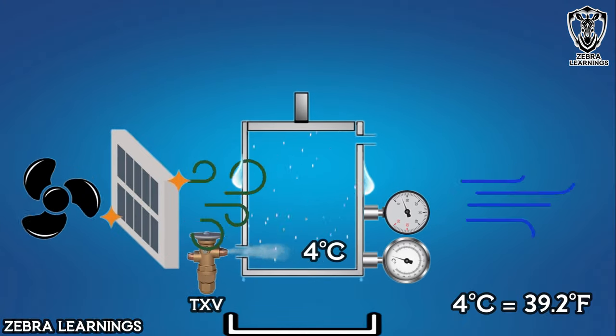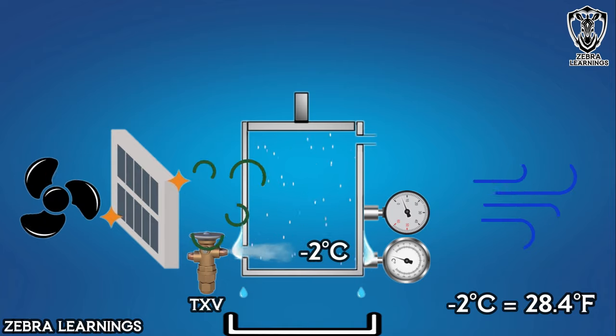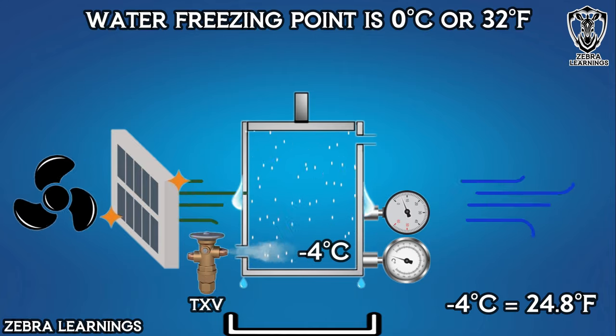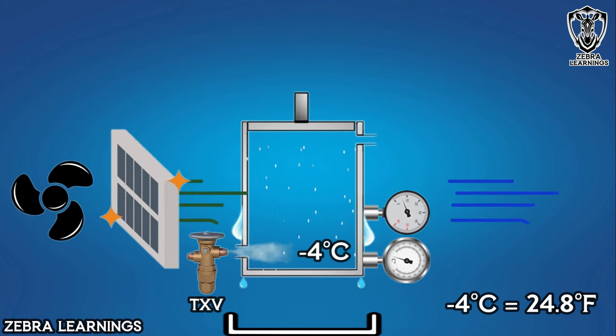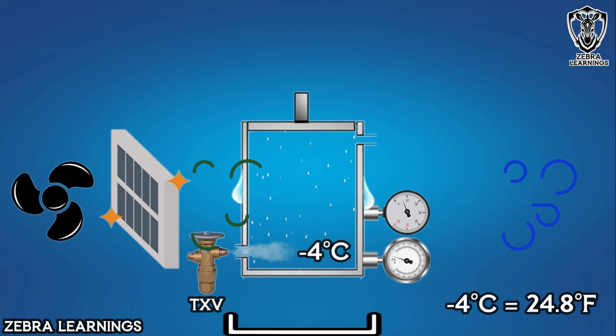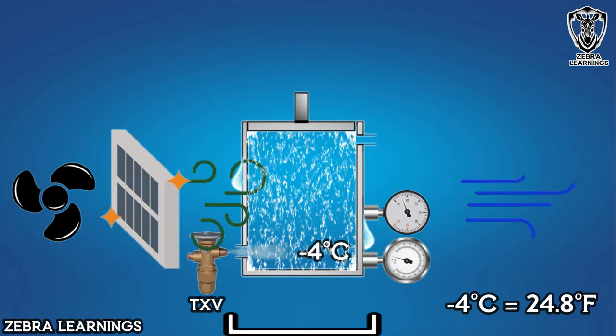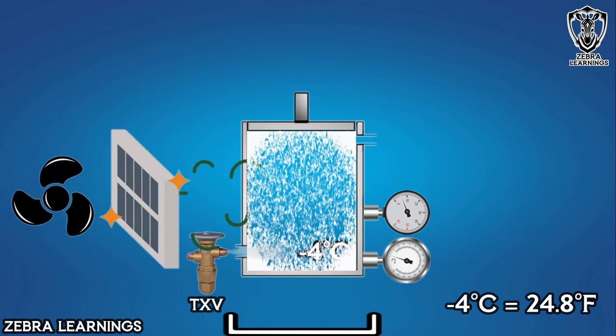Refrigerant which is already at 4 degrees Celsius will further decrease to minus. Now, the evaporator coil temperature is minus 4 degrees Celsius. The freezing point of water is 0 degrees Celsius. Since the evaporator coil is at minus 4 degrees Celsius, the water from condensation on it freezes. It spreads little by little and freezes all over the evaporator coil. As the frozen evaporator coil becomes blocked, the air cannot pass through, so the temperature of the room increases.